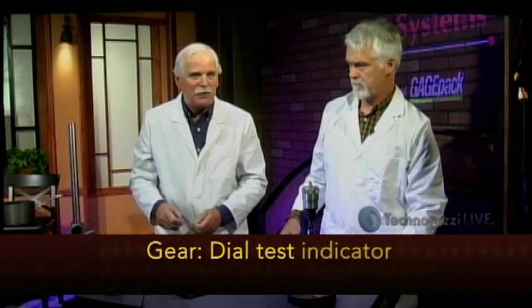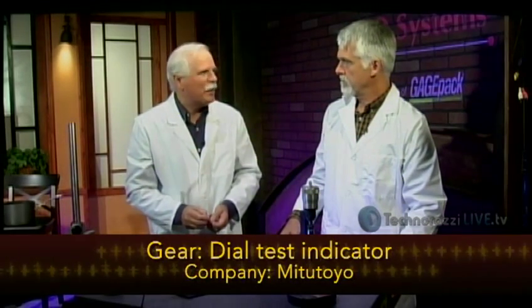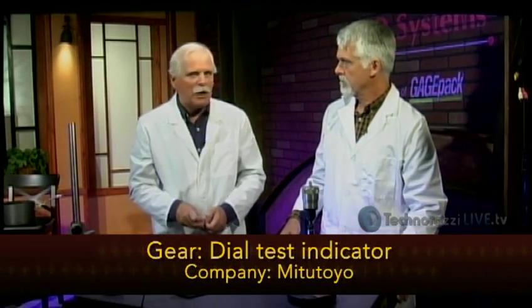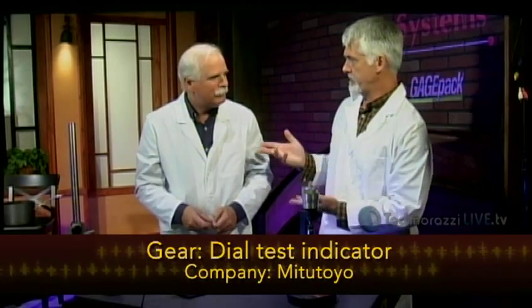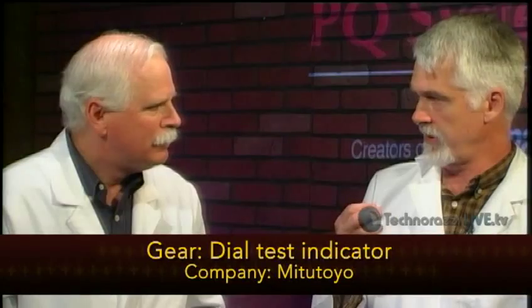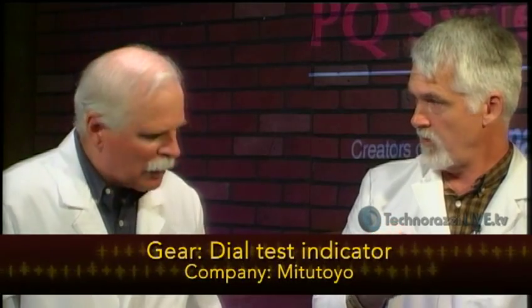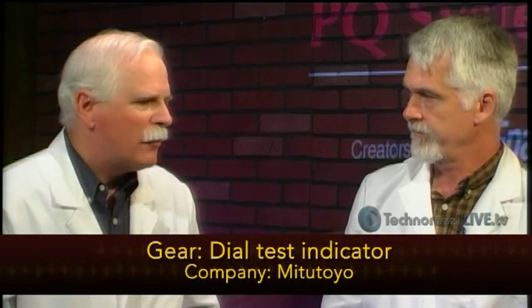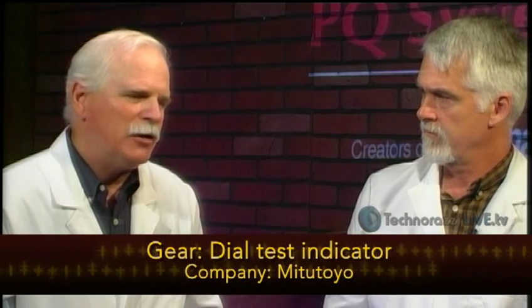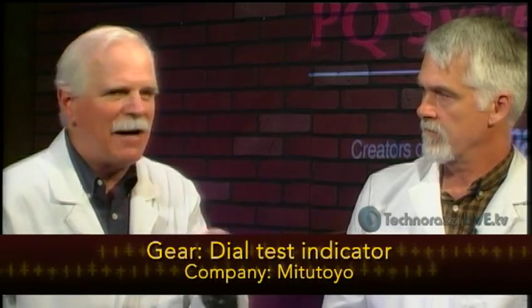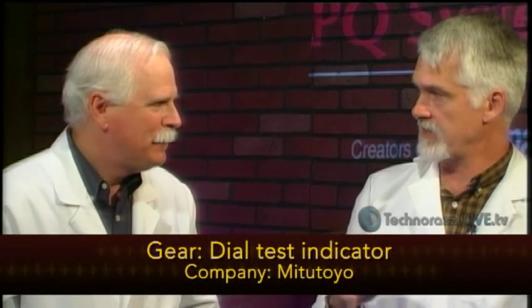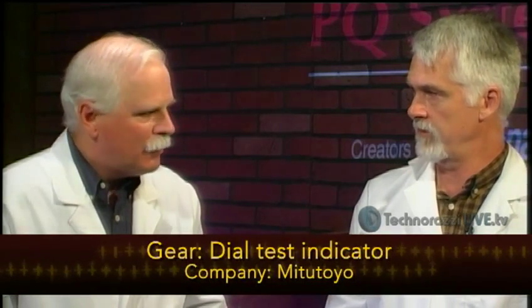The better quality balls will hold up. They're usually carbide. You can get them in ruby. You can get them in all different materials from a good contact point maker. And part of your job in a calibration lab is to actually inspect them, under like a microscope or something like that? We usually will. If we're on site in the field, we might use a handheld magnifier, but you'll see it's bright and shiny when they're good, and as they wear, it starts getting dull. Then you start noticing a flat spot. Eventually it looks like a half moon. And even a little bit of a flat spot is going to make a difference on the accuracy of your reading.